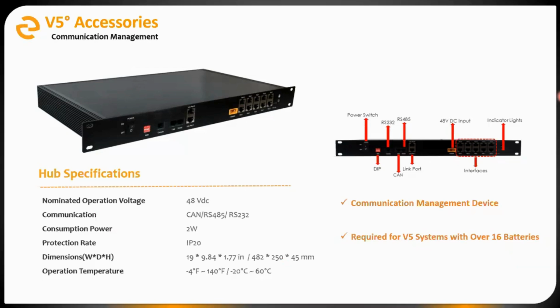If you're using a closed loop inverter like Solarc, Lux, Mega Revo, or Victron, and you have more than 16 batteries, say 18 or 20, at that point it's required to use this hub accessory. What this does is facilitate communications between multiple groups of batteries. This doesn't have battery cells in it, and it doesn't do anything with the battery BMS. It's really just a communications management device, and it's used for the other products in our ESS family as well.